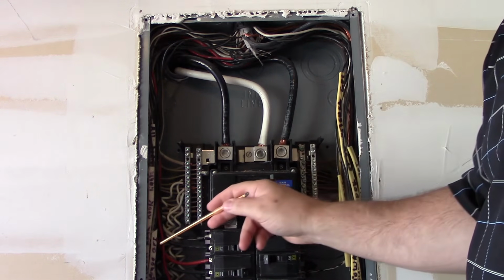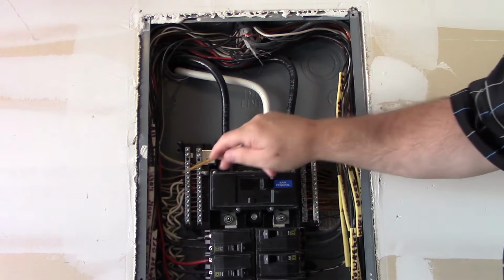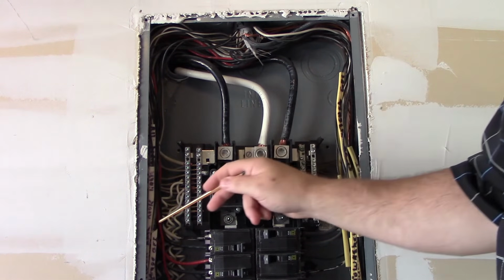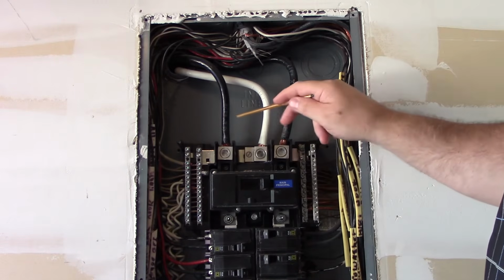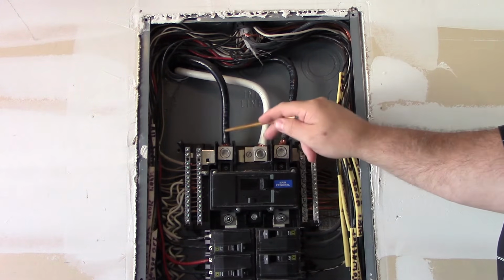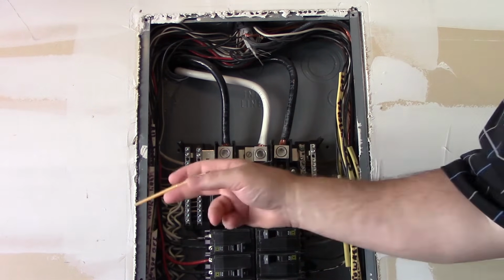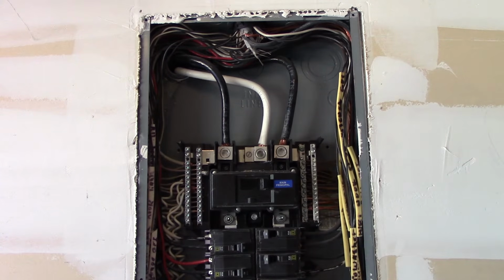All right, and the size of the conductors that terminate onto this bus or even these lugs are over here in this legend. It tells you the maximum and minimum sizes that can go into the various lugs and terminals. So that's what's important about that over there.